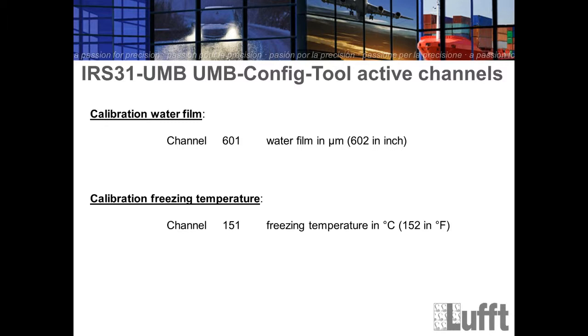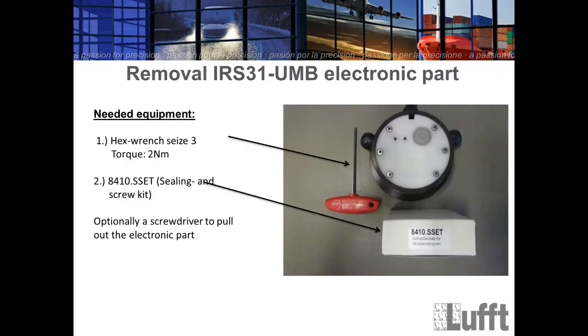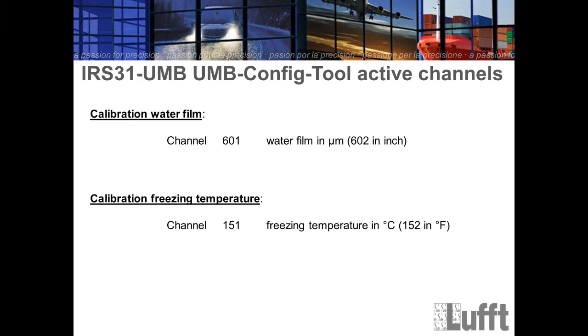Then you have the calibration freezing temperature, and this channel is channel 151 in the UMB channel list for the IRS31, and that's the freezing temperature in Celsius degrees. If you need the degrees Fahrenheit value, you can also activate 152, which is the Fahrenheit unit. These are the channels. So that's all for the calibration. Normally now we have done it.